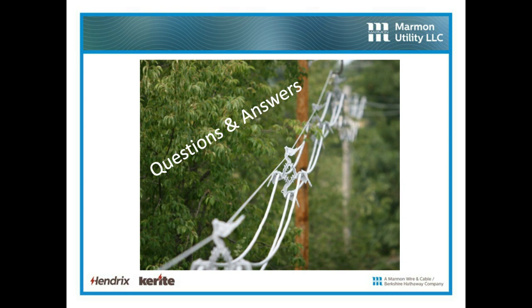Secondly, you will see a lot of the municipals here in the Northeast. They're using spacer cable because they have double or triple circuits down the main feeder line substation exit. They're also having their telephone wires or their cable wires on those same poles. And to do that with bare wire would, number one, be impossible on that same pole line. And number two, even if they did it, would be vastly unsafe because to work on one line, you have to de-energize the whole darn thing, de-energize the whole metro area. And I could probably think of other applications if you gave me time, Mike. Okay, great. Thank you, Brian.